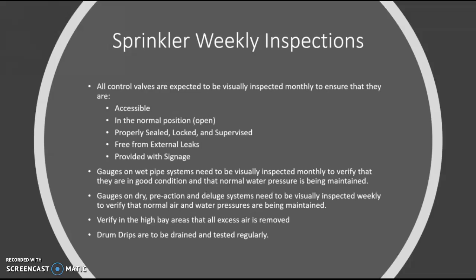We're going to verify in the high bay areas that all the excess air is removed. The excess air in the system creates rot and issues for the system to have problems down the line. So by opening up the top of these pipes, we're going to remove all that excess air and stop wear and tear from happening. And then drum drips are drained and tested regularly.